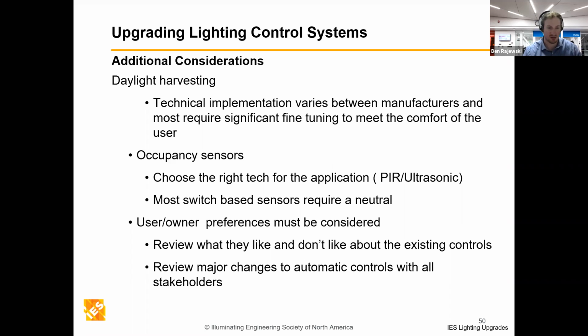The other thing I'd add is to remember the voltage you're working with. A lot of lighting we've done has been 347 volts for the past few years, but now LED has made it preferable to do everything at 120 volts. So if you're upgrading your lighting controls, make sure everything's compatible with the 347 you're working with. And if you have some combination of 347 and 120, make sure your panel can actually handle that properly, so you're not dealing with dual voltages in a panel. That's just something to keep in mind on the voltage side.